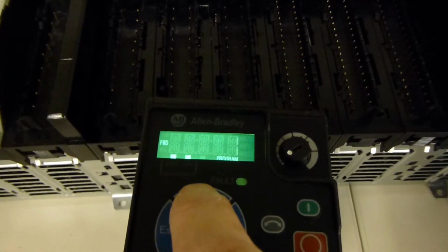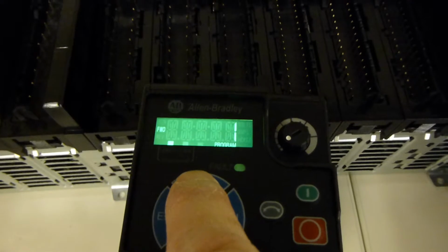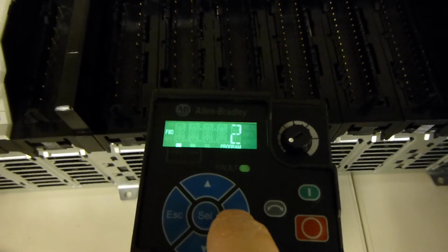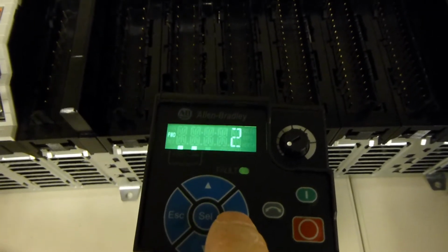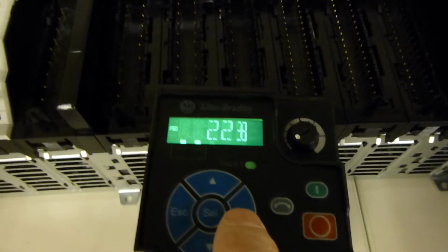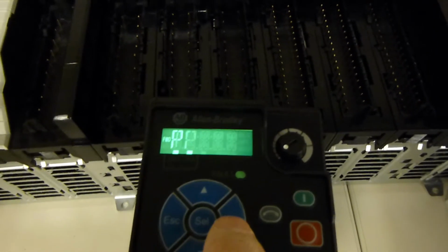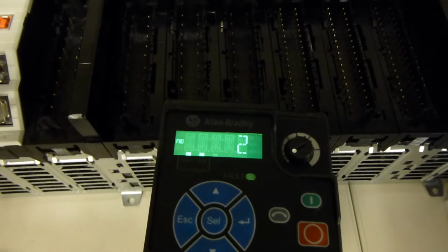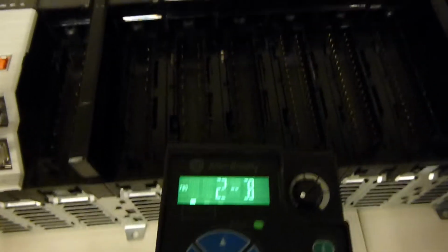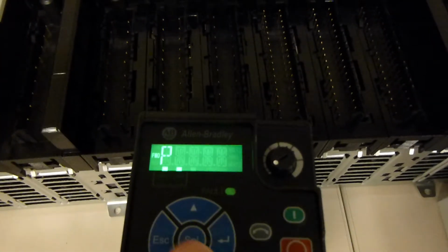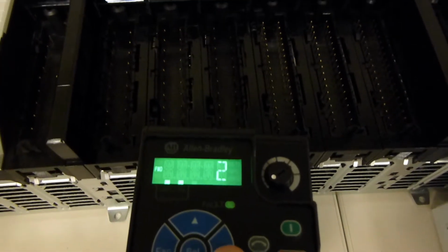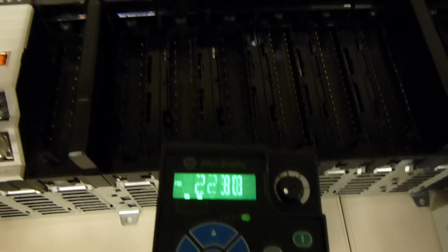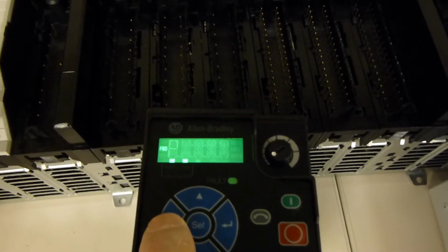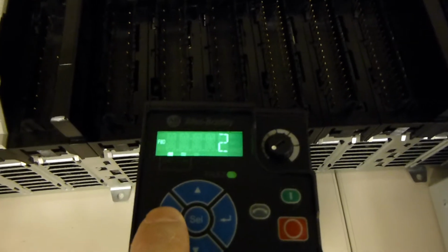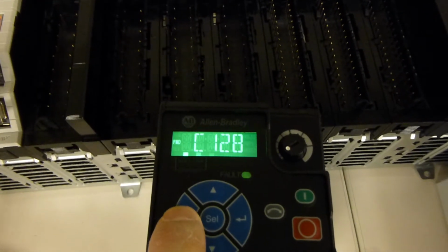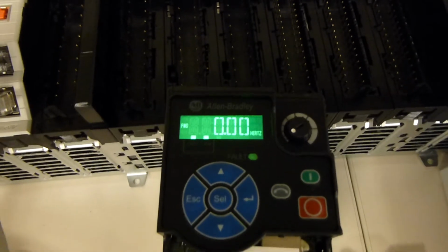There is no number 3, it just scrolls back to 1. It may be available in a future release, but for now, this is firmware revision 5, which is the latest as of May 2017. In the future, it may be a feature where you can actually see it selected in the PowerFlex. So we've got number 2 set for BOOTP. We'll go ahead and accept that. Escape out.